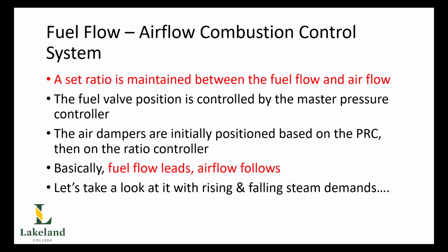Now, with regards to the leader and the follower, this refers to the philosophy of the control system. That is, in this particular system, the fuel flow is the leader and the airflow is the follower, meaning that fuel flow will determine the airflow. What this doesn't mean is that fuel flow adjusts first, then airflow adjusts second.